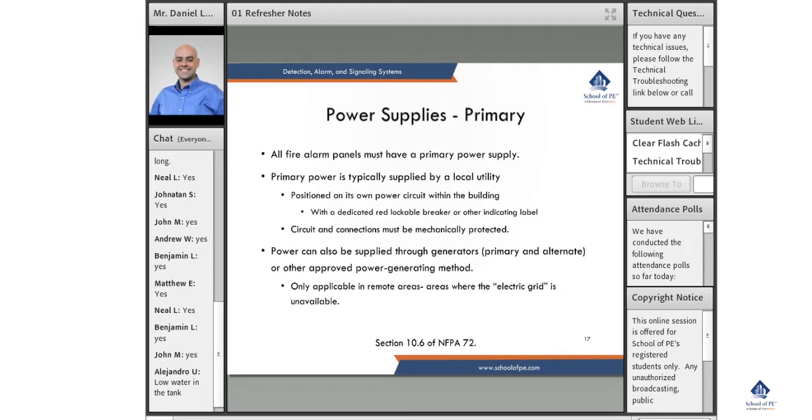It's with a dedicated red lockable breaker or other indicating label so that any responders, any maintenance personnel know that this breaker is a fire alarm, a life safety dedicated circuit.